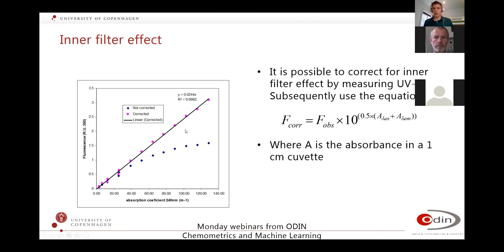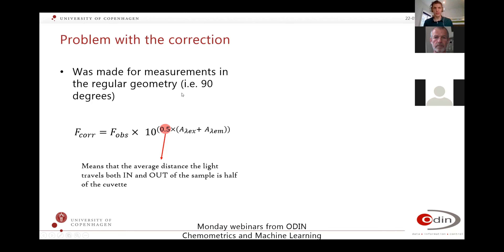Normally it is possible to correct for these inner filter effects by measuring UV-Vis and using the correction equation. This states that you use the absorbance measured with UV-Vis to do the correction. The UV-Vis must be measured with the same cuvette as you are measuring your fluorescence with. This correction was originally derived based on a regular 90-degree geometry. The factor 0.5 in the equation indicates that you're going halfway through in both directions of your cuvette — half a centimetre in and half a centimetre out again.